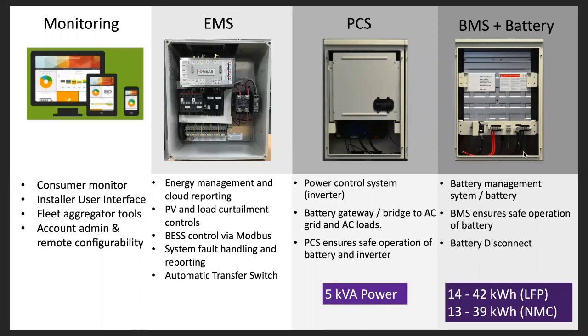And then the DC component or the DC cabinets basically just consist of the battery modules themselves and their BMSs. The BMS ensures a safe operation of each of the battery modules, as well as there being a battery disconnect inside the first battery cabinet. For the LFP systems, the capacity ranges from a minimum of 14 kWh up to a maximum of 42 kWh. And for the NMC-based product, it goes from 13 to 39 kWh.